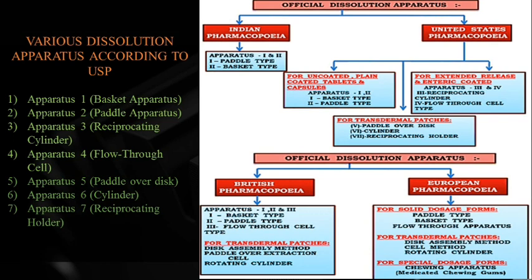USP Apparatus 3 (reciprocating cylinder) and 4 (flow-through cell) are used for extended-release and enteric-coated tablets. Apparatus 5, 6, and 7 are used for transdermal patches. British Pharmacopoeia: Apparatus 1 is basket, 2 is paddle, 3 is flow-through cell; for transdermal patches they use disc assembly, paddle over extraction cell, and rotating cylinder. European Pharmacopoeia uses paddle, basket, and flow-through cell for solid dosage forms, and disc assembly, cell method, and rotating cylinder for transdermal patches.